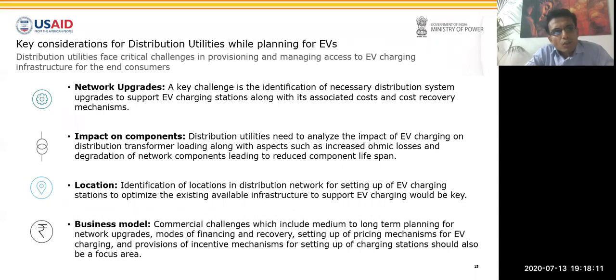The third is location - where in the network to prioritize EV charging locations is an important factor. Some feeders might get overloaded, while others have substantial margin even for the next 5 to 6 years, so you prioritize those locations with a strategy for laying out the distribution network.